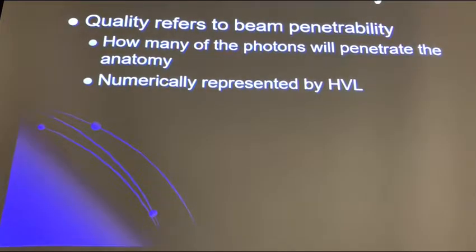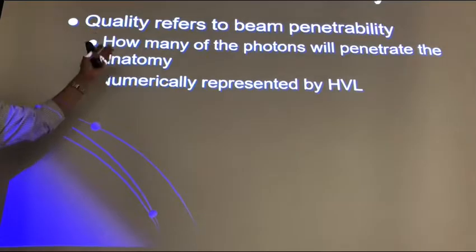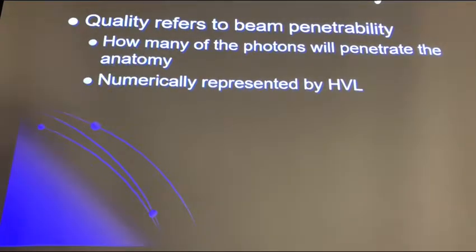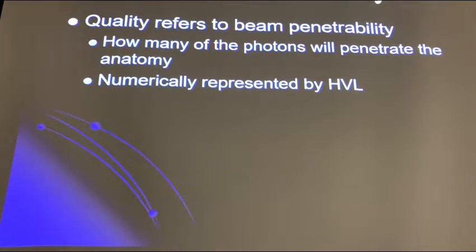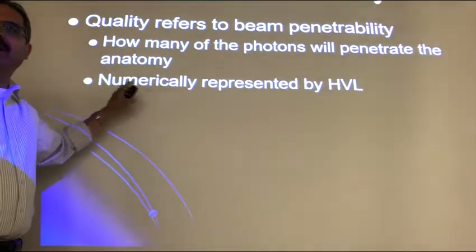Quantity and quality: quality refers to the beam's penetrability, and it's mainly controlled by KVP. How many of these photons will penetrate the anatomy — how many will actually go through the patient? Numerically, this is represented by something called the half value layer.